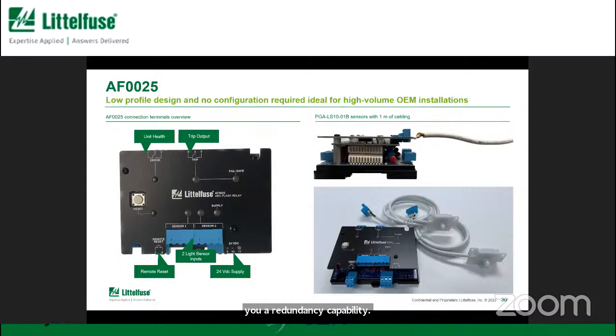So that again gives you a redundancy capability. And a new one that's relatively recently been added is the AF25. And as you can see with the model numbers going down, this one is again reduced in size. So it was made to be very thin, so a very compact package. And this one has 2 sensors, and it removes some of the other functionality that may not be needed for a very simple application. So if there's a high volume panel application where you just need 1 sensor, maybe 2 in a small panel, but space is very, very tight, then the AF25 could be a very cost-effective way to add arc flash protection.